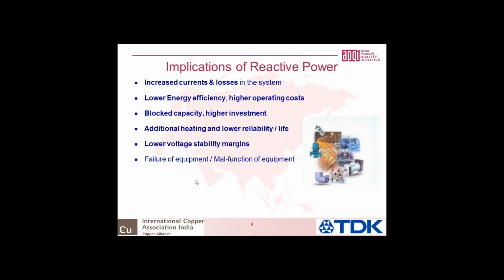Apart from that, you have certain other implications like failure or malfunction of equipment. Over the last 25 years, I've seen quite a few cases where people have reported equipment malfunction or failure because of low power factor or a combination of power factor and harmonics. You have poor operational efficiency or unplanned outages. It could have neutral burnouts. You can have under voltage conditions, which could lead to cascaded tripping, or you can have poor operational efficiency. There are also cases I've seen where there is poor quality of the products manufactured.